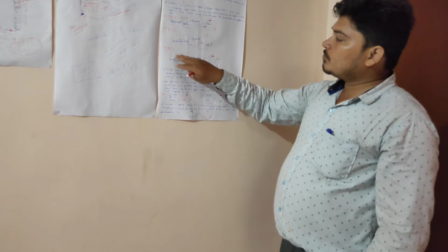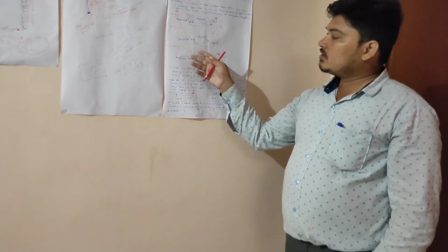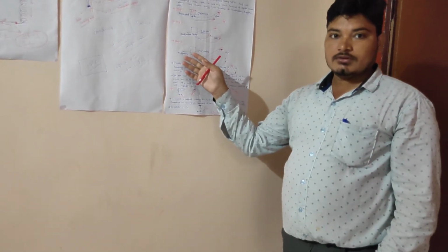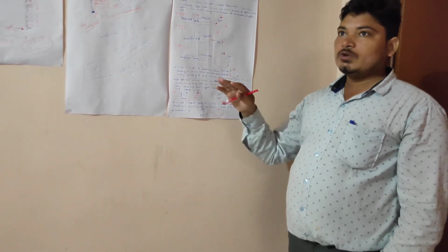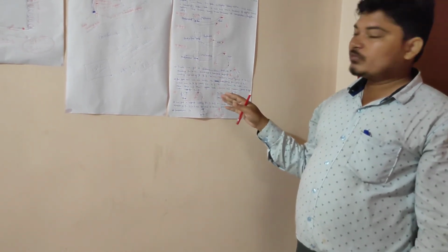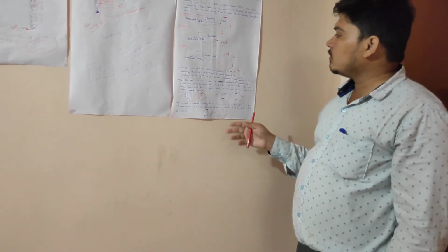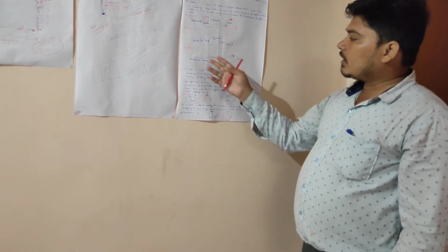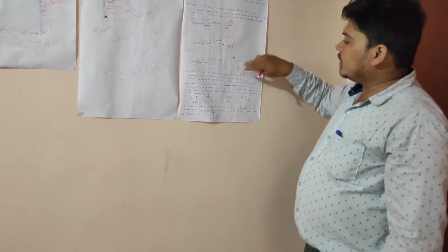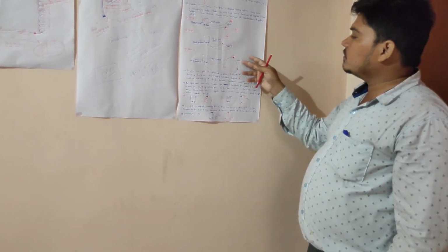In the last step, step 3, the digital clamp meter will be the same. The continuity mode, there are no changes in the digital clamp meter, and this compressor has 3 electrical terminals A, B, C, and between A and C we get 17 ohm.